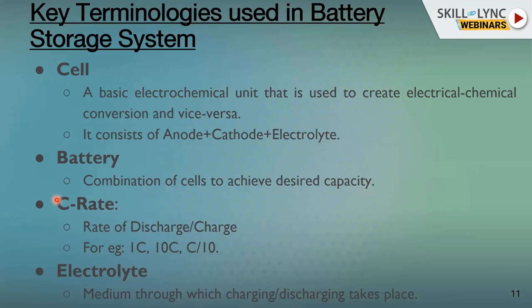To understand C-rate: if a battery has a 65 Ah charge capacity, operating at 1C means it can discharge 65 amps for 1 hour. At 10C, it can supply 650 amps, but the discharge time decreases to 6 minutes — the more current demanded, the less time the battery lasts. At C/10, it discharges at just 6.5 amps but lasts 10 hours. Note that this is not exactly a linear relationship — at 10C the battery may exhaust in under 6 minutes, while at C/10 it may last over 10 hours.